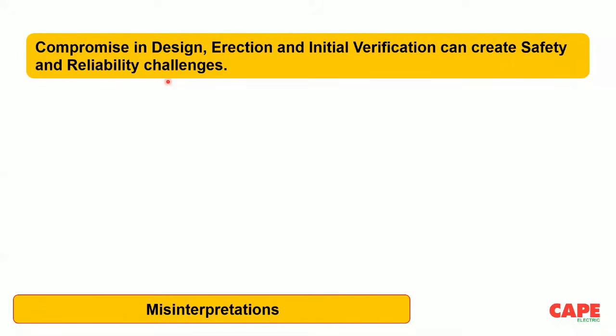So due to these reasons, which were told in the previous slide, any compromise in design, erection, and the initial verification can create a serious safety and reliability challenge. In the sense, after installation, you cannot change it, you cannot switch off, you cannot go and test, you cannot access the wiring. So don't compromise in the design, in the erection, and in the initial verification of your electrical installation, because if you have a perfect electrical installation, it will serve for at least 40 years, or 30 plus years.